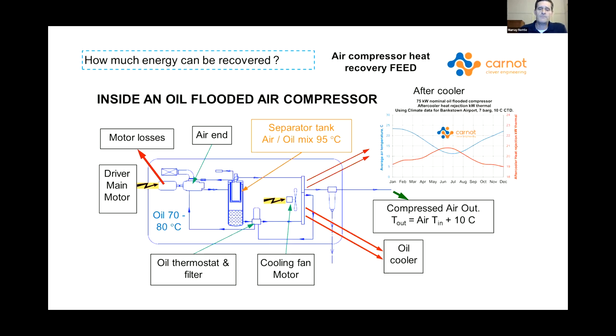Now you've heard people talk about, Selwyn was talking about 80 kilowatts, 80% of the heat going to the oil cooler. It is variable. It depends upon how the compressor is operating. And as you can see in that graph, the temperature being lost and the energy lost through your after cooler varies with the temperature of the day and the humidity of the air coming into the machine. So if you've got wet, humid air coming into the machine, you've got to condense a lot of water, you've got to reject a lot of heat in your after cooler. So the actual heat loads vary with the time of the day, with the season, and with how heavily loaded your air compressor is.